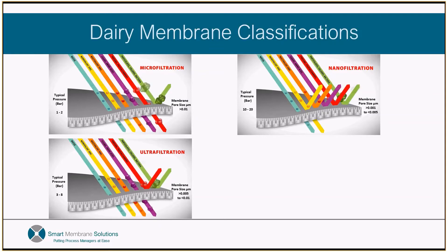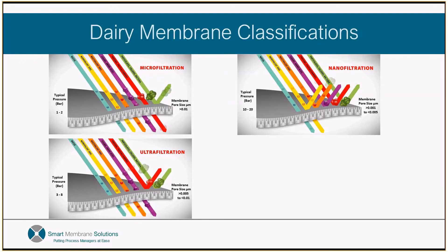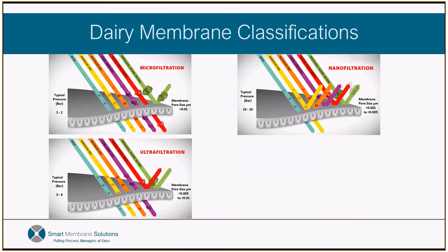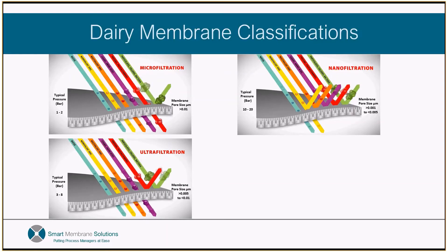Nanofiltration is becoming more and more prevalent on the back of a UF or RO process to further allow higher total solids retentates to be produced whilst maintaining acceptable permeate flux levels. Due to the increase of osmotic pressure in NF streams, system pressure often starts at no less than 10 bar, which is around 145 psi, and runs higher.